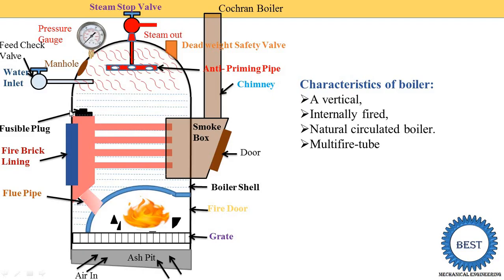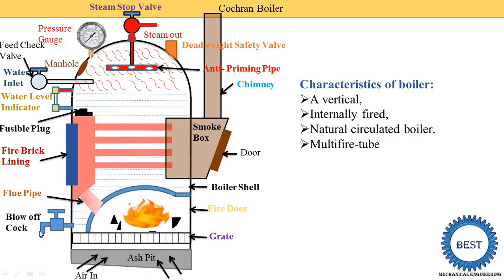Here is the dead weight safety valve, and here is the fusible plug — at the end of the video, I will explain what the fusible plug is and why it is used. The water level indicator shows the water level inside the boiler. The blow-off cock is used to empty the boiler shell of water when cleaning is needed, and then the person enters through the manhole for inspection or cleaning.